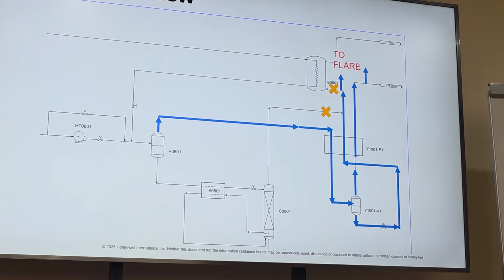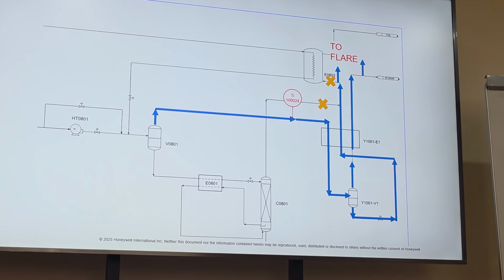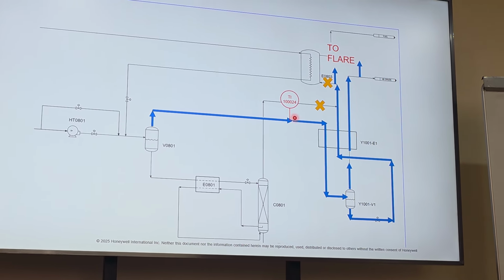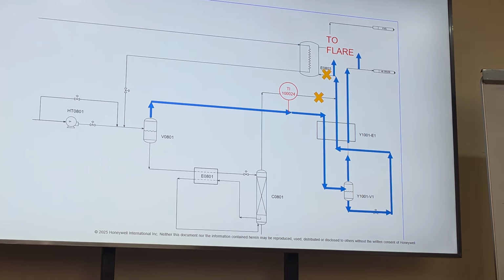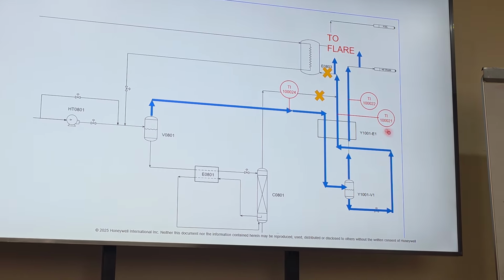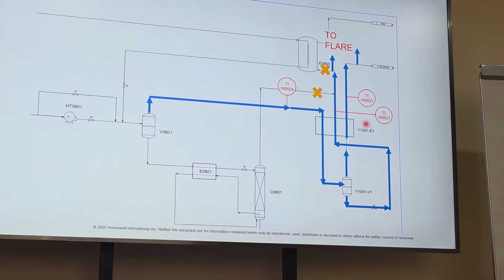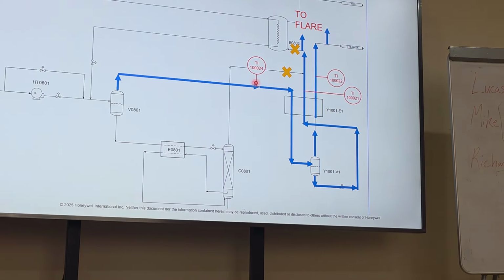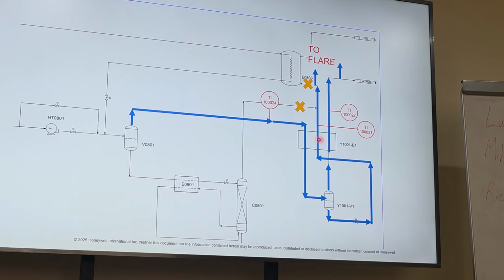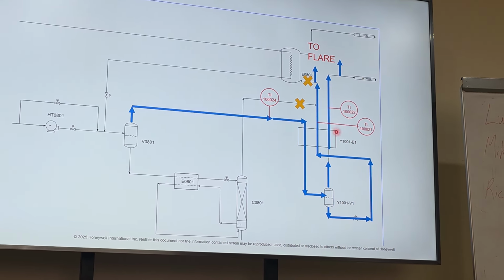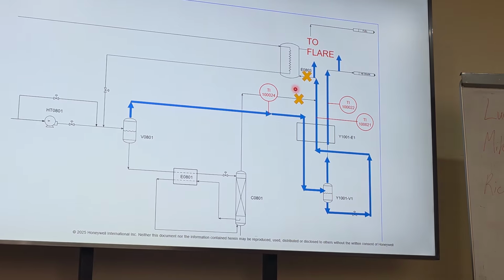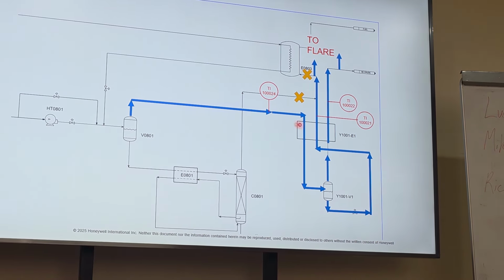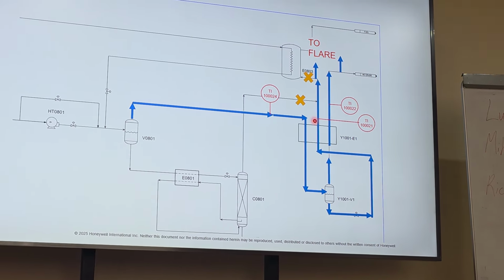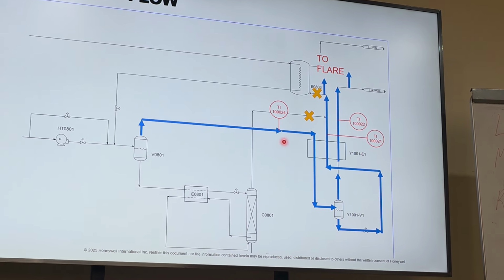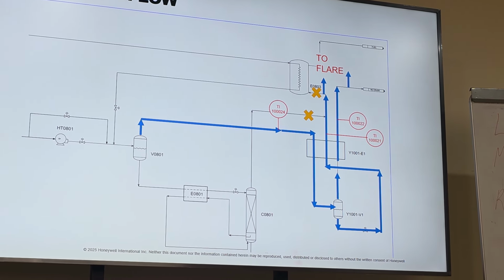Okay, normal flow direction. We're going to monitor the temperature at TI 1024, and then we're going to also monitor the temperature at 22 and 21. Those are out of the heat exchanger, okay? Because what do we want? We want this temperature in to be within 28 degrees C of these temperatures out, okay? Because this is the delta T we're talking about. This pass in versus these two passes here should not be more than 28 degrees C different.